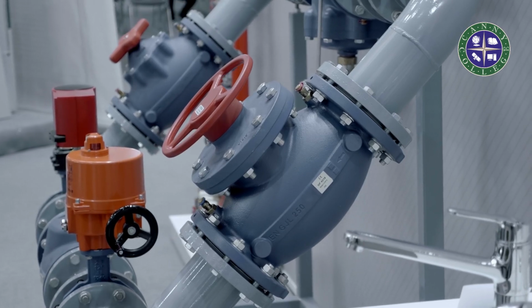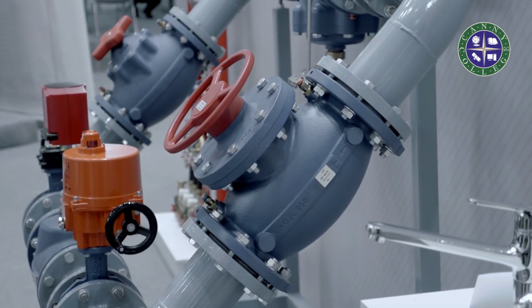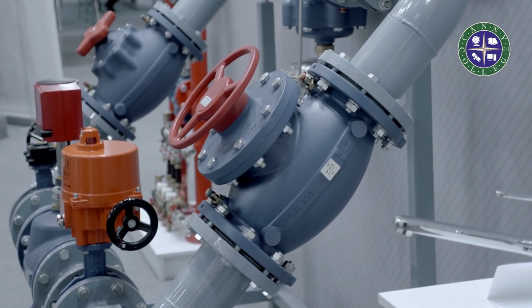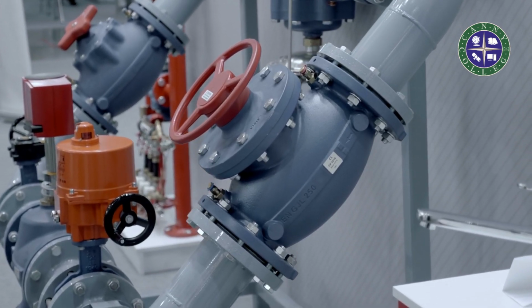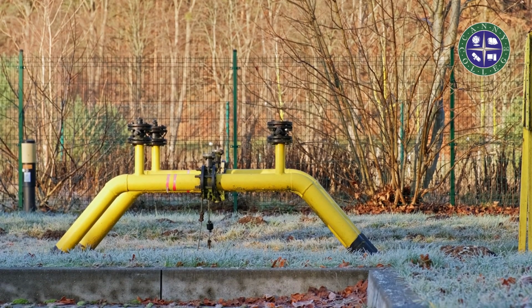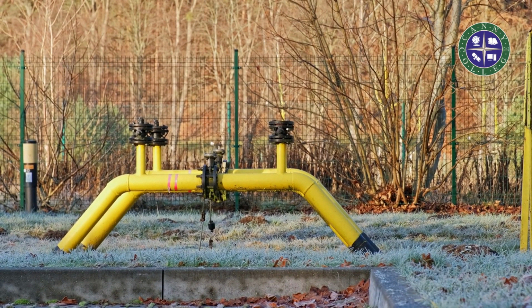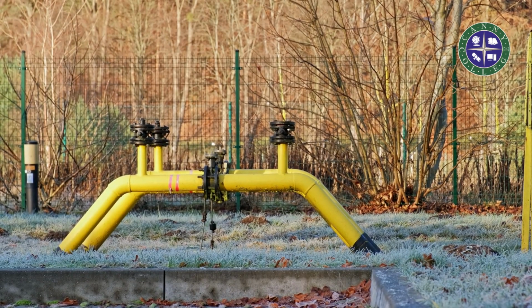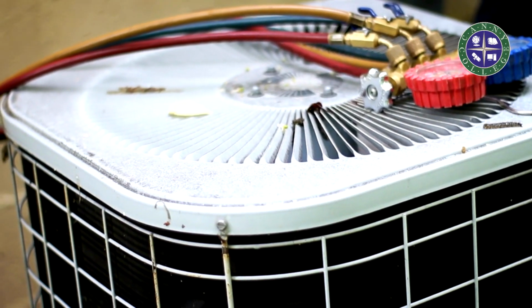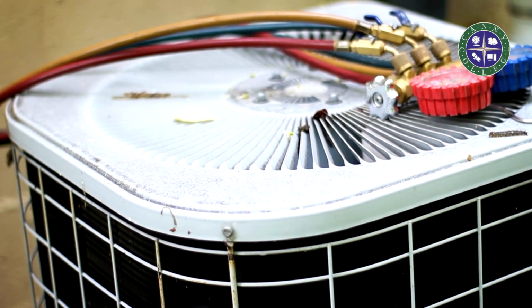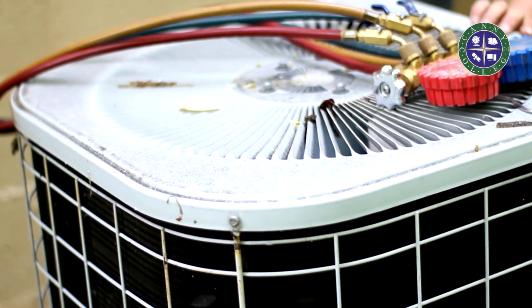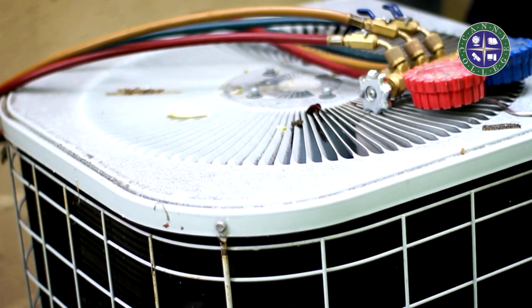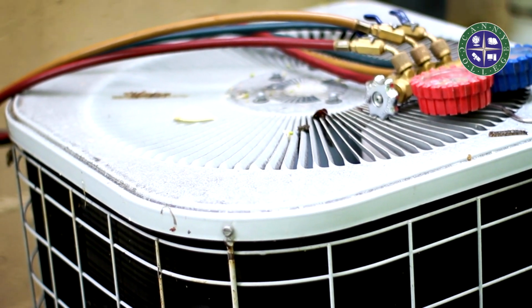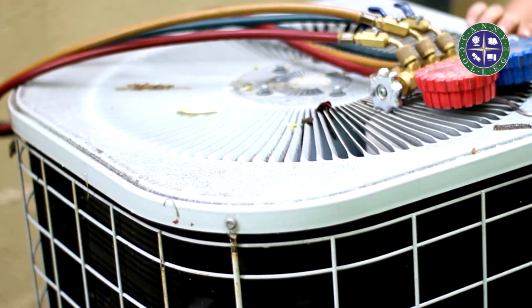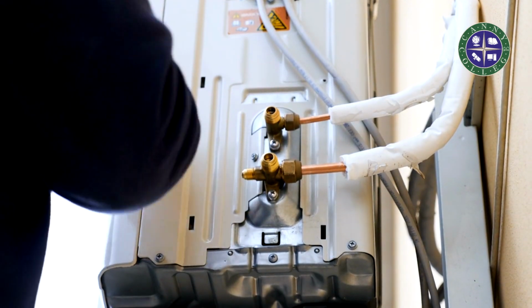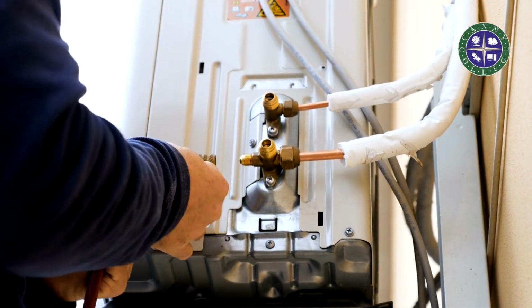3. By front seating the king valve, the refrigerant can be contained within the system and prevent any leakage during maintenance or service procedures. This is essential to safely and effectively carry out tasks such as repairs, system checks, or component replacements. 4. Properly adjusting the king valve by turning the stem clockwise to the front seat position plays a crucial role in performing a manual pump down procedure accurately and securely, allowing for the safe removal of refrigerant from the system. It is a fundamental step in maintaining the integrity of the system and ensuring proper refrigerant management.